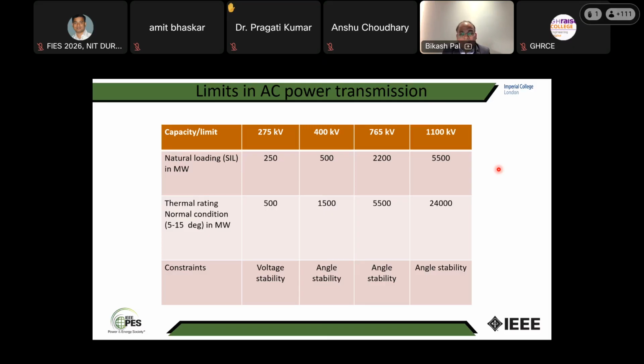For 275 kV, it's about 500. For 400 kV, it is 1500. And again, for 765 kV, it is 5500. And 1100 kV, it is 24,000. But it is not exactly going to be like that. That depends on the conductor geometry: how many conductors you have, conductor spacing, and then the inductance and the capacitance, because all these things lead to that V square by the square root of L by C value. So 250, 500, 2200, 5500 is just like a sample one.